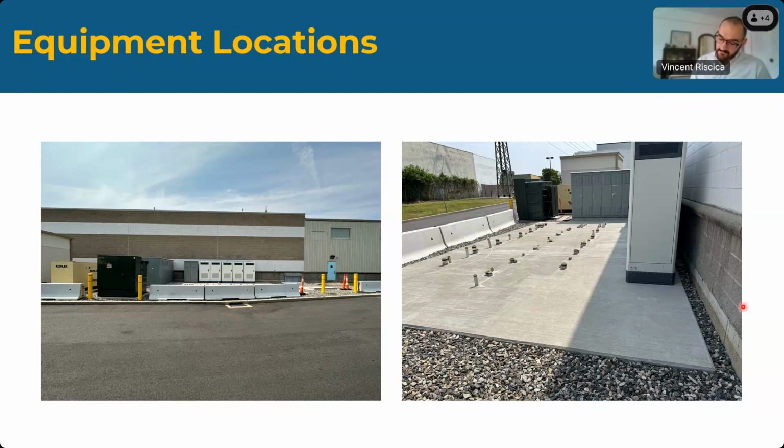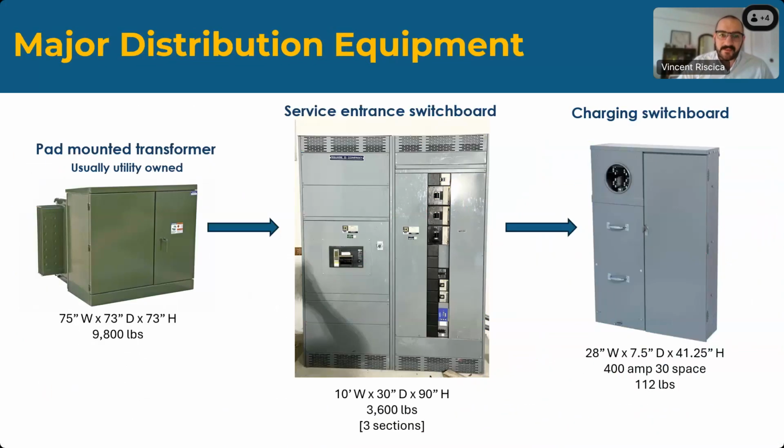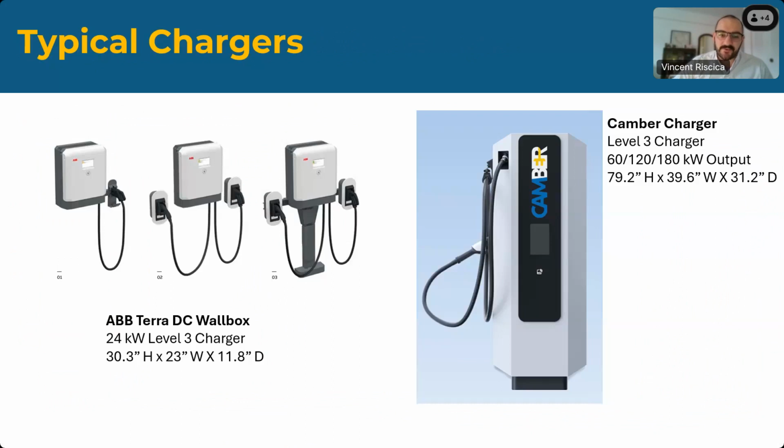And then you also mentioned, and I think it's important to keep reiterating this point, that the charger itself and the dispenser can be the same piece, but they can also be separated. There are some maximum lengths that you'd want to stick within in terms of the distance between the dispenser and the charger itself. Could you talk a little bit about that? Yes, the max distance between the charger and the dispenser is 400 feet. And the max distance from the dispenser to the bus is about 27 feet. And that is with an extra extension on the cable. Standard is about 20 feet.